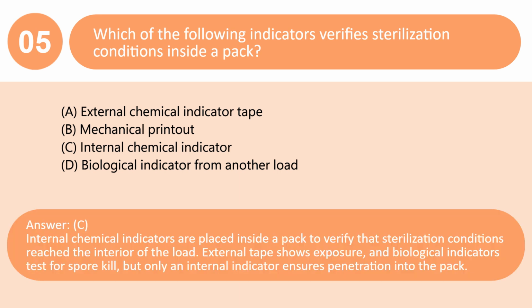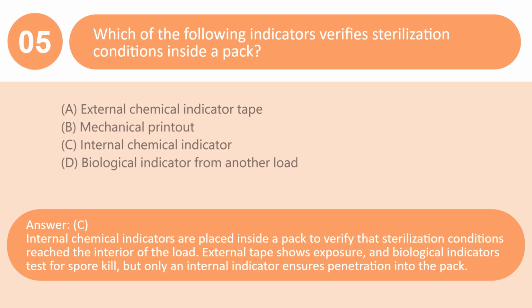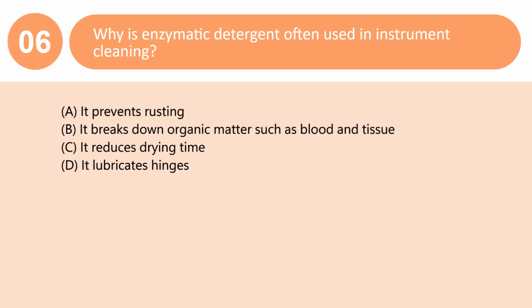Answer: C. Internal chemical indicators are placed inside a pack to verify that sterilization conditions reach the interior of the load. External tape shows exposure, and biological indicators test for spore kill, but only an internal indicator ensures penetration into the pack.